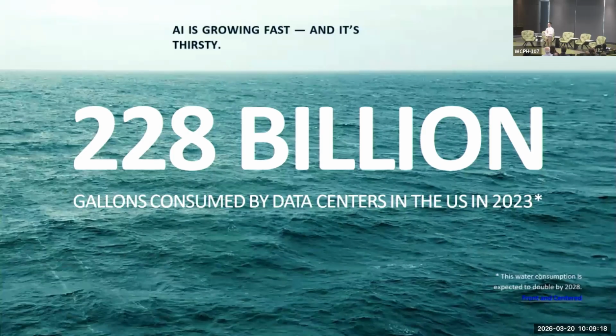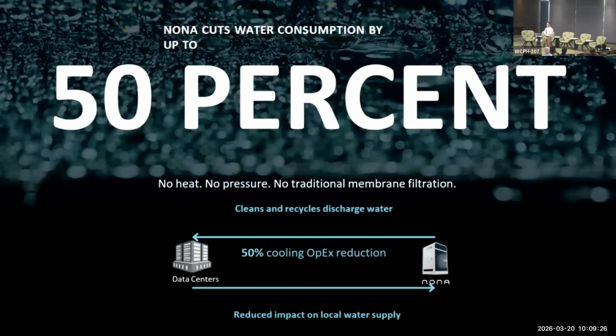AI uses a lot of water, primarily through cooling, using evaporative cooling towers. Basically what happens is there's a loop of water cooling all the equipment in the data center that is sprayed on a panel on the roof, and through latent heat the water evaporates and removes that heat.